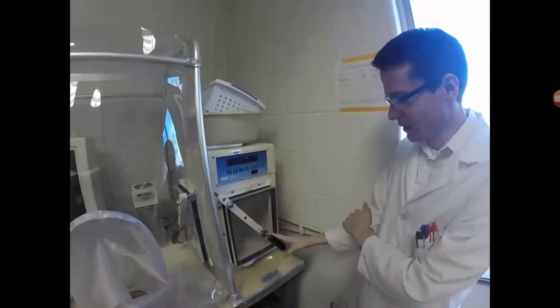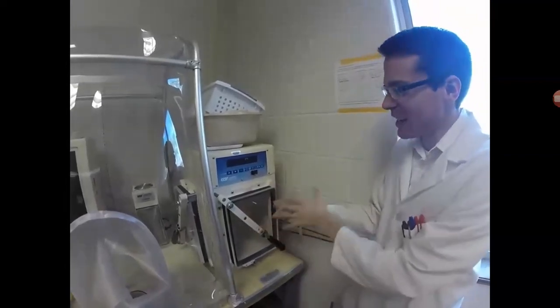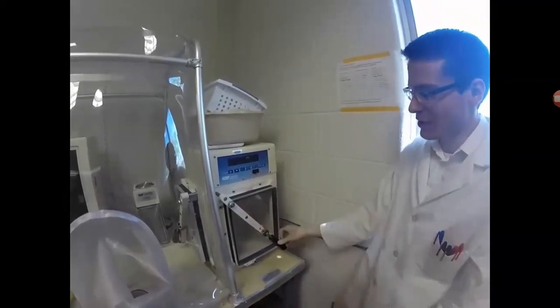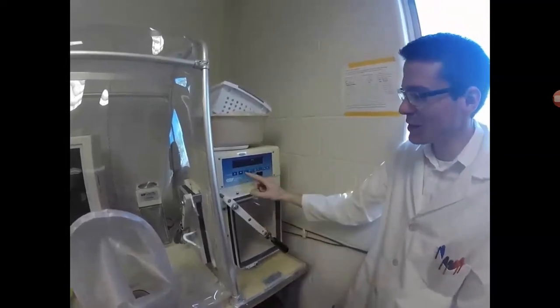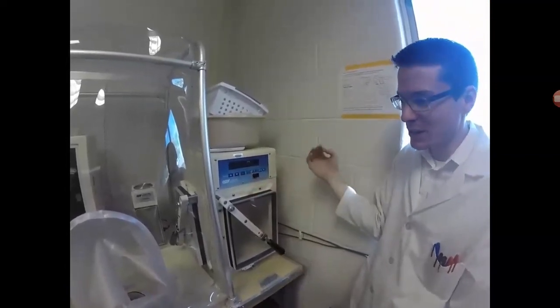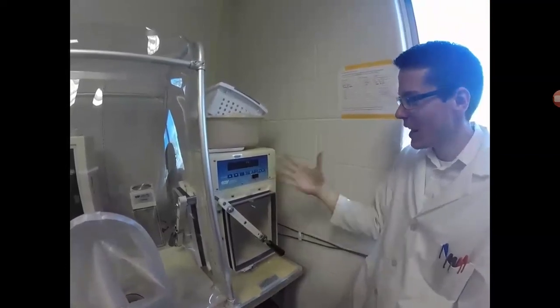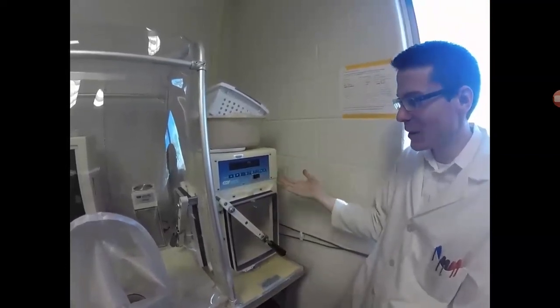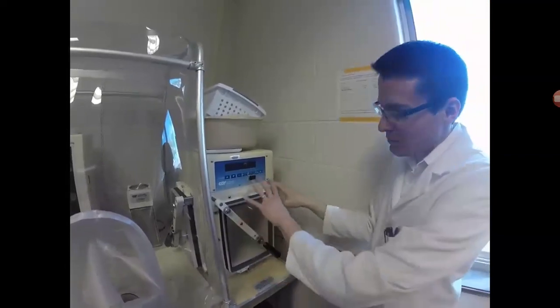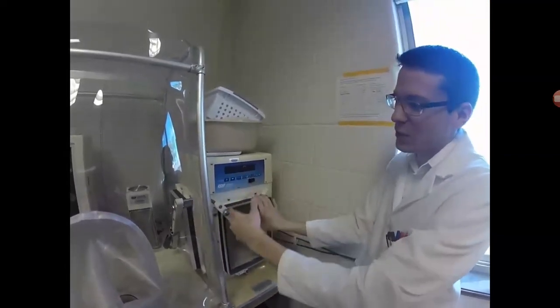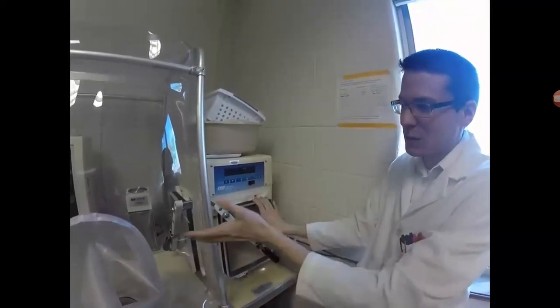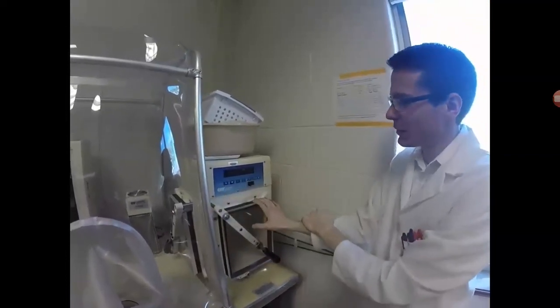you want to open this door. You'll then place the materials inside. You'll close this door, make sure that it's latched. And then you press start to run the 3 vacuum cycles and then the 3 gas purge cycles, at which point it will beep and say it's anaerobic. When it's anaerobic, then you can, with the outside door closed, open the inside door, take the stuff into the chamber, and then place them inside, and then again close the inside door.